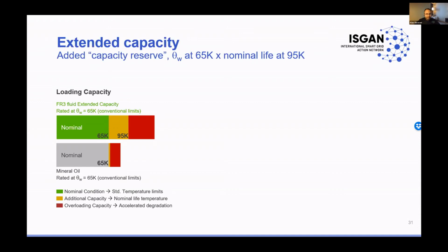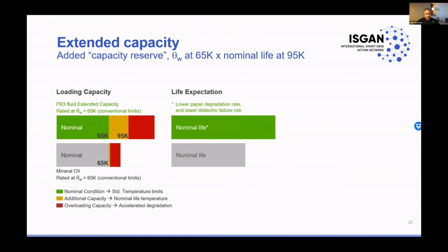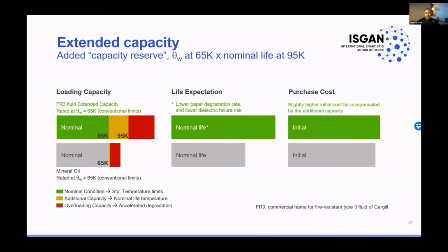If you could click one more time, Fernando. The other dimension that we will check is life expectation of the transformer. Since you will be running the transformer most of the time around the 65 Kelvin, you will have a longer life in a natural ester unit in comparison to the mineral oil unit, even if you use this higher loading capacity as a normal loading condition, right? One more time, please. And also, there is the aspect of reducing the degradation rate or the likelihood of a dielectric failure by keeping the insulating system drier throughout the life.